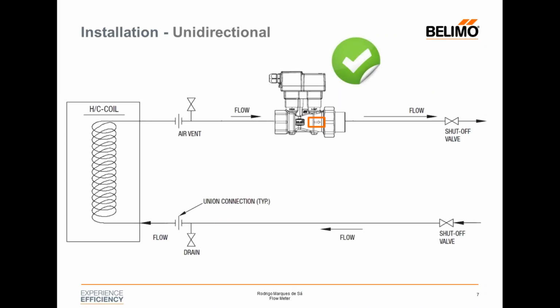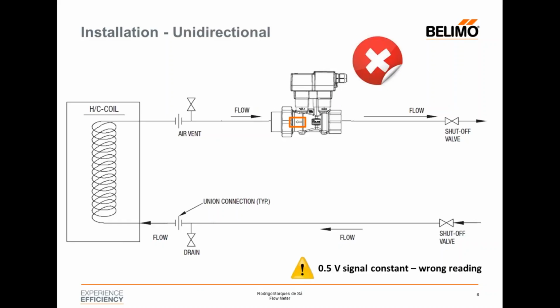About the installation, it's a unidirectional flow meter, so you just have one side or one way to mount that, so you have to respect the arrow you can find on the body part. If not, since it's unidirectional, you're going to receive a signal of 0.5 volts, a constant one, meaning a wrong reading, a wrong value. So be careful when installing that flow meter.